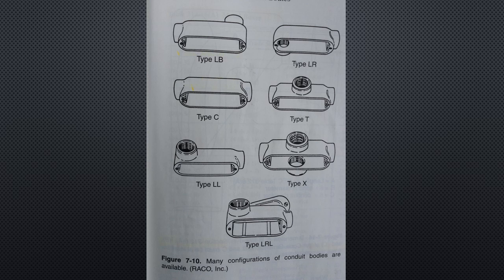The code points out that capped elbows, service entrance elbows, and similar fittings cannot contain splices, devices, or taps. Conduit bodies are subject to the same code rules as boxes with regards to filling, splicing, tapping, and device installation. Very few conduit bodies have adequate volume to accommodate splices, taps, or device installation unless they are oversized by two to three times the largest conduit entering the conduit body. Conduit bodies that are not marked with their capacity cannot contain splices, taps, or devices.